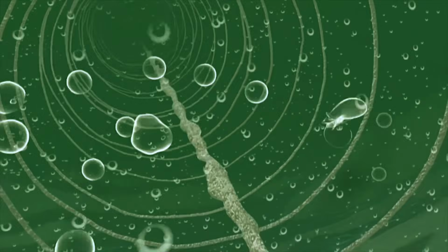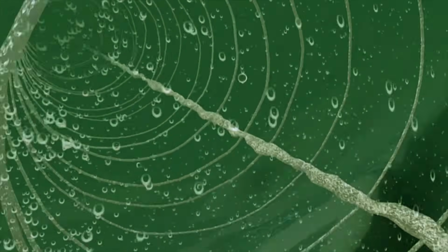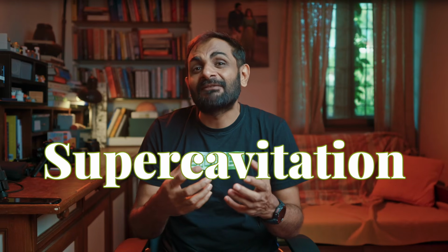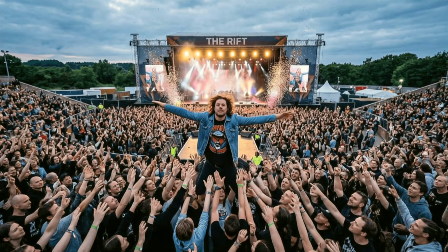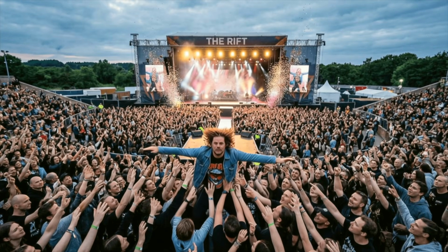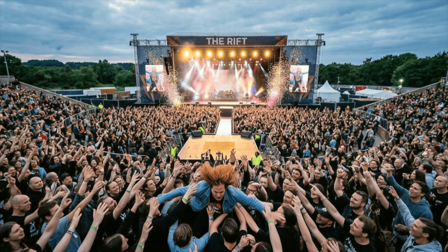As you try to increase the extent of cavitation, what happens is, as these bubbles start getting formed, they start merging together, and it's called supercavitation. And when that happens, they sort of start cushioning each other. It's almost like when somebody jumps on a crowd and the crowd absorbs that fall, something like that. So what happens because of that? The collapse rate drops, right? So the cavitation drops, and therefore the process stops working for water treatment. So how do you fix that?